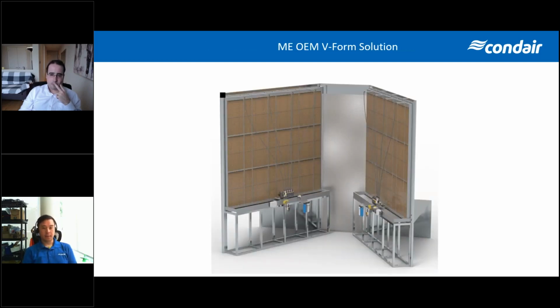Very similar here in terms of the previous design where the client was using bypass dampers to control the leaving air condition. But in this case, we were somewhat limited in terms of the amount of media that we could put in perpendicular to the airstream. So what we've done here is just put the media in on an angle to increase the free area or media area that we've got in the airstream. And that just helps us to bring the overall pressure drop down, the velocity on the media down, and increase our evaporation efficiency. So really just trying to get more media into the airstream by putting it in on an angle versus just perpendicular to the airstream.